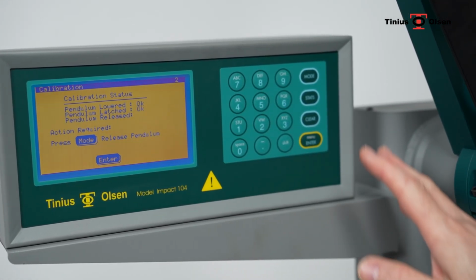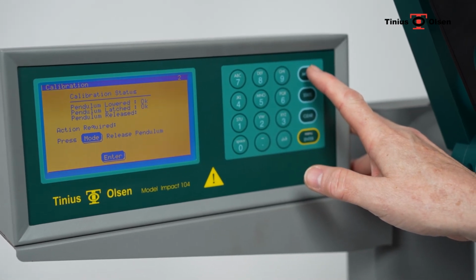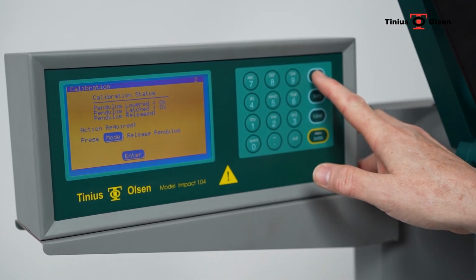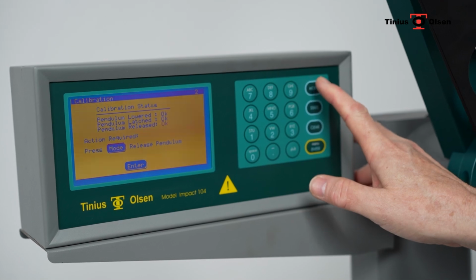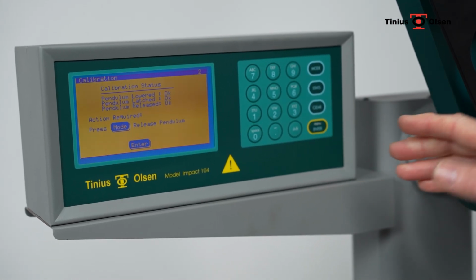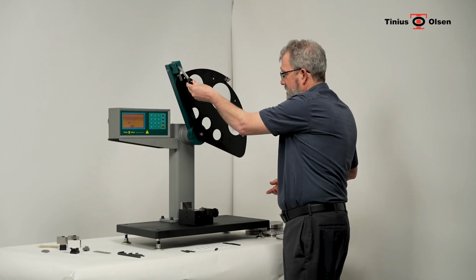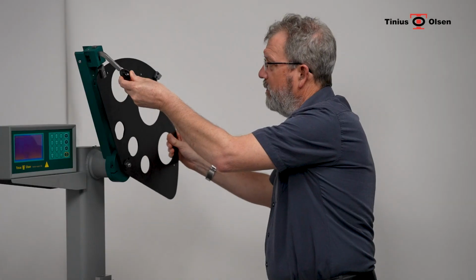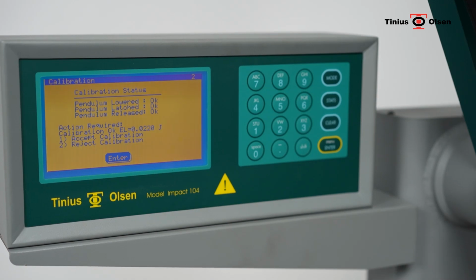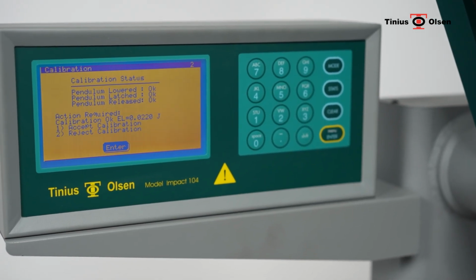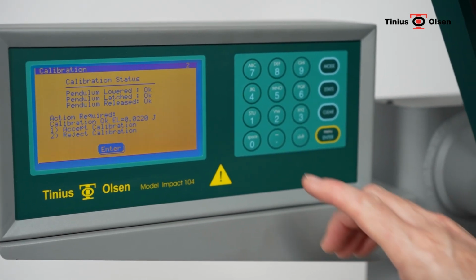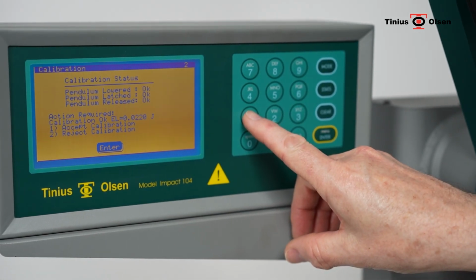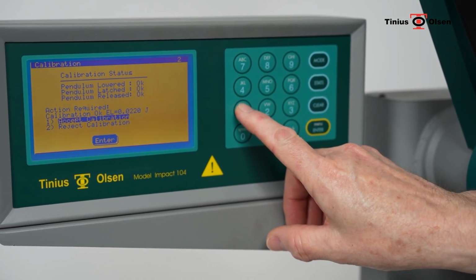Now in this instance, when we press the mode button, it monitors the motion of the pendulum to observe what energy loss there is on one free swing. We release the pendulum, it does one free swing, we capture the pendulum and we relatch it. The screen will actually display the energy loss for that one swing, and then we can either accept or reject the calibration.